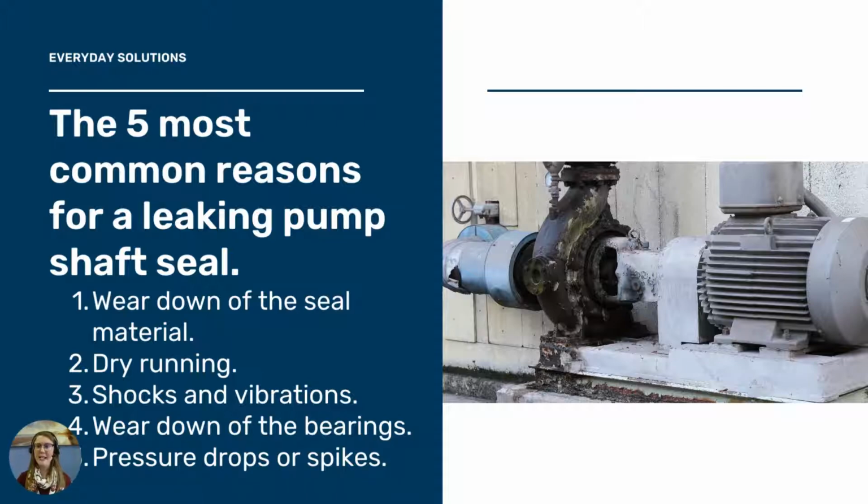Now, the second reason is a pump seal normally needs fluids to lubricate the materials around that shaft. So if there are no fluids available to lubricate it, the seal is going to run dry, which is going to cause a lot of friction and heat. And in return, that seal is going to either burn up, melt, or become damaged, which then causes the fluids to leak due to that pressure. So even if it runs dry for a few seconds, this could damage your seal. So you want to have fluids either running through it, unless it's a specific pump that can be run dry, then you won't have that problem, or make sure that everything is lubricated, especially even with those Haynes lubricants that you could use as well.